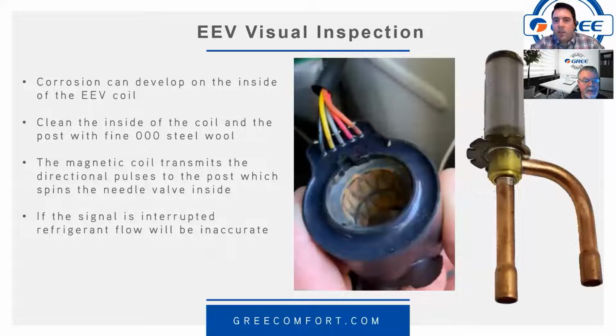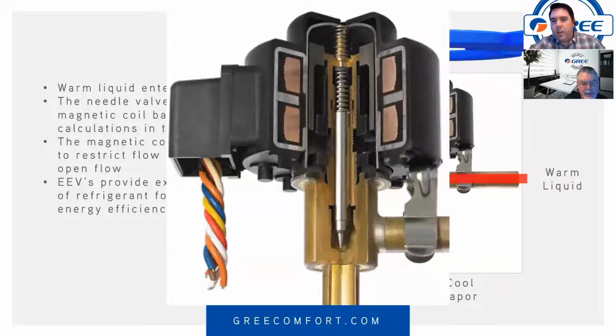So as you can see from the opening there, if you forget to deburr your flares and a piece of copper happens to make it past the strainer, then you could have a blockage there, couldn't you, Keith? Sure. Yep. And that's why we don't allow desiccant dryers, brazing without nitrogen, a number of things that can cause problems in here. One tiny little piece of debris can cause that thing to stick and not function properly.